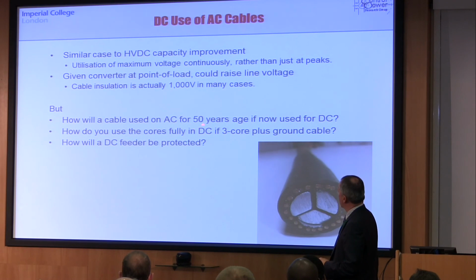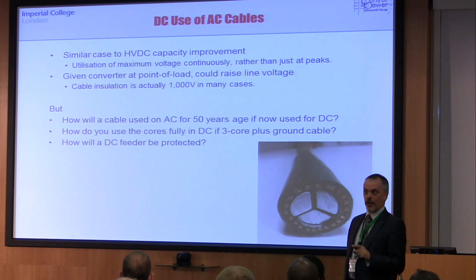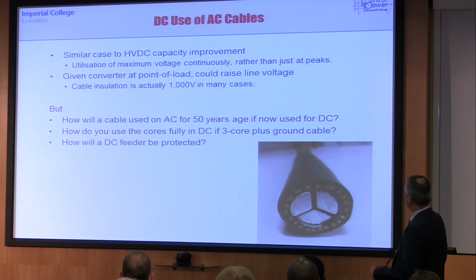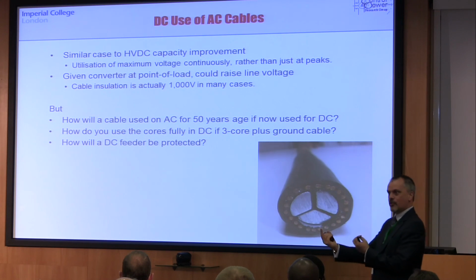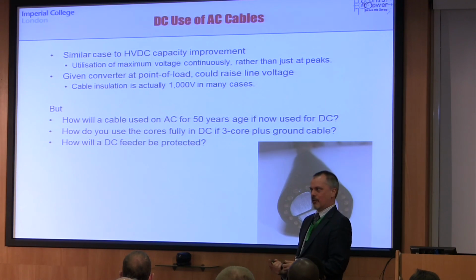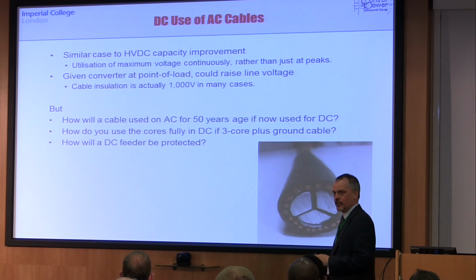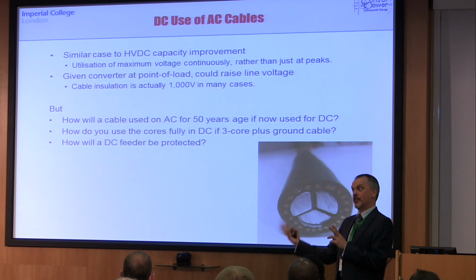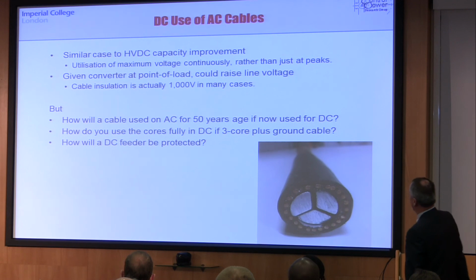But some of those cables have been in the ground used on AC for 50 years, and we're now going to start using them for DC and then try to do an aging model to know when we have to replace them. And nobody really knows what's the aging model of a cable that's had decades on AC and is now used on DC. It is a big issue.